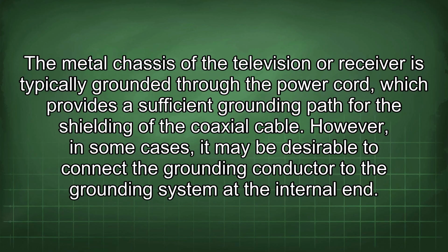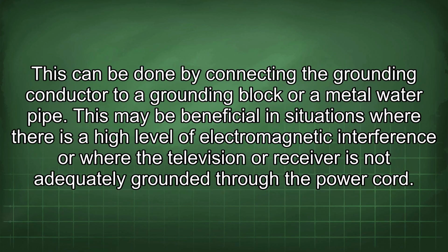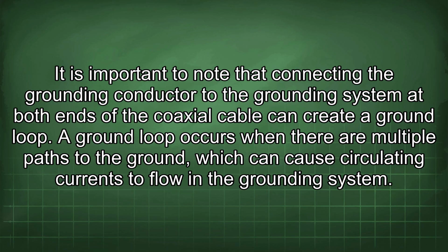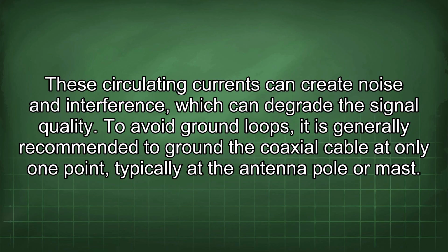However, in some cases, it may be desirable to connect the grounding conductor to the grounding system at the internal end. This can be done by connecting the grounding conductor to a grounding block or a metal water pipe. This may be beneficial in situations where there is a high level of electromagnetic interference or where the television or receiver is not adequately grounded through the power cord. It is important to note that connecting the grounding conductor to the grounding system at both ends of the coaxial cable can create a ground loop. A ground loop occurs when there are multiple paths to the ground, which can cause circulating currents to flow in the grounding system. These circulating currents can create noise and interference, which can degrade the signal quality.